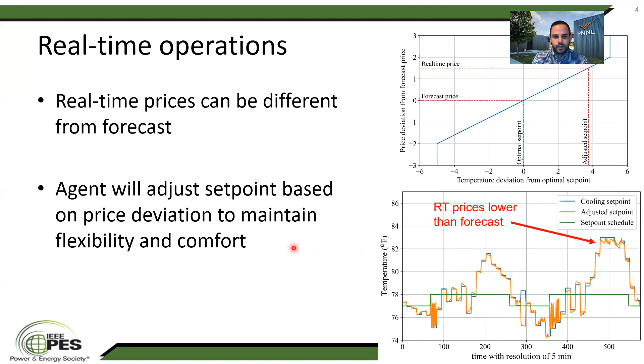To finalize the presentation, as we mentioned, including this type of agent control is important and necessary if we want to allow flexibility in the demand from the HVAC, but also this level of control is required because we need to coordinate between comfort and saving. The key functionalities we highlighted here are the model estimation, the schedule optimization, and the control implementation. We saw that the simplified linear model was able to give us good accuracy. The optimization model gave us a set point schedule that reduced the consumption without really sacrificing user comfort. And the real-time correction was able to handle the shifts in the real-time price, which adjusts the set point accordingly.